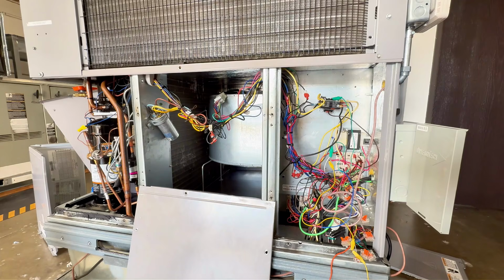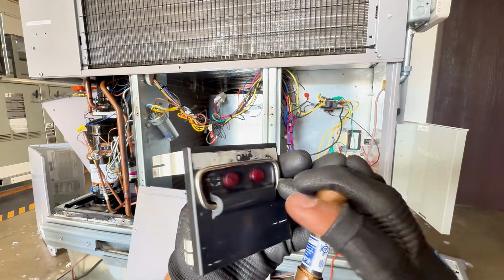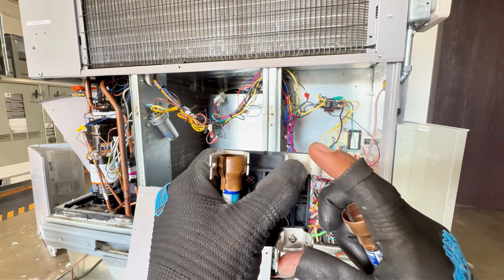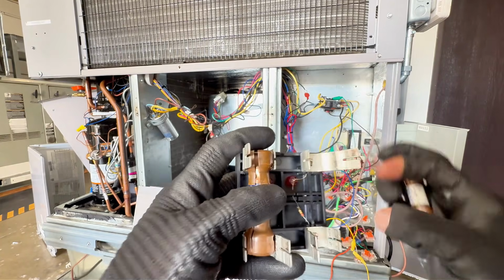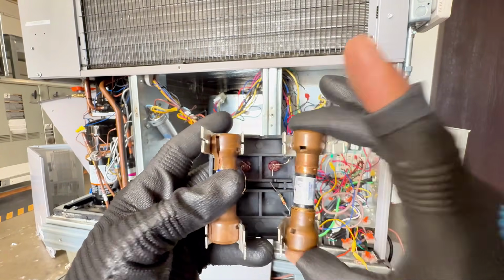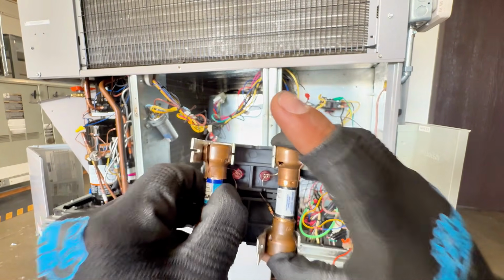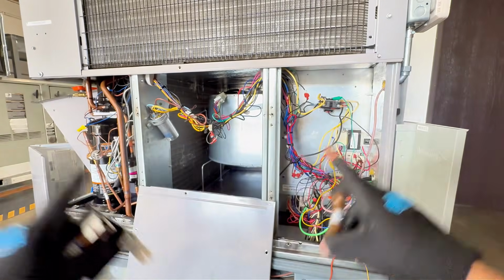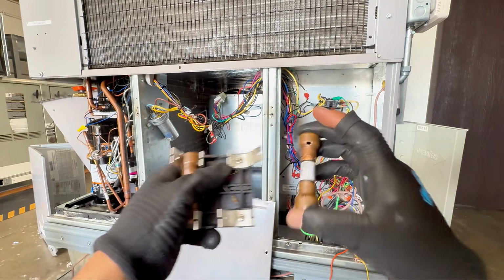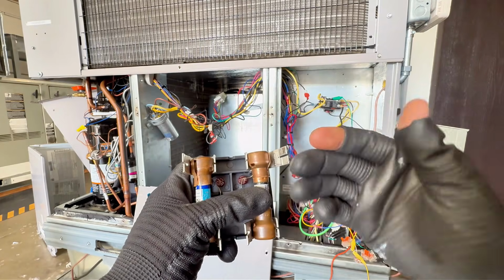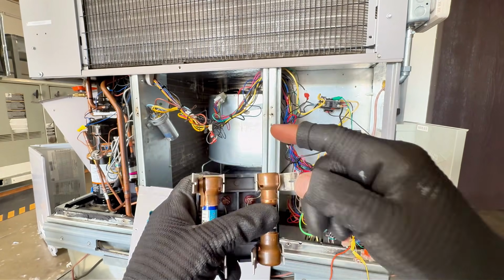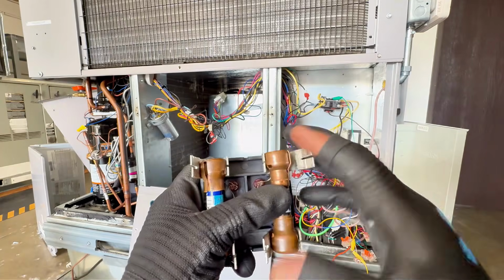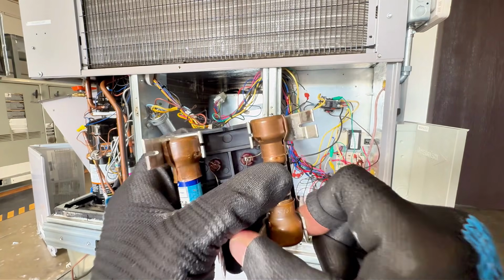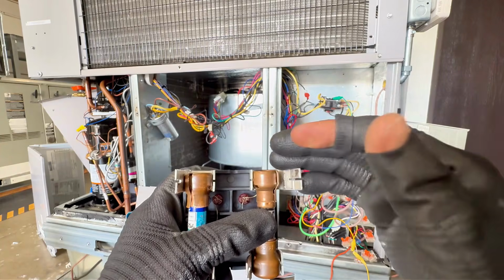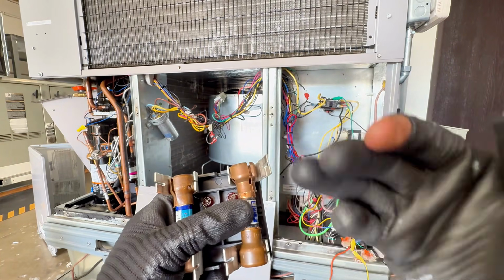I did forget to mention this in the previous clip. As part of your maintenance, if you go to your disconnect and the forks are really loose, that's gonna be an issue. So for example, you see right here, I'm gonna put this fuse. There's a lot of play compared to this one, right? So everything can be okay with the actual unit itself, no shorts, but your fuse can go bad over and over because there's a lot of resistance, right? There's a lot of current going through, and it has to be tied like a nice path. But if it's loose, more resistance, more heat, and it can cause your fuse to go bad over and over.